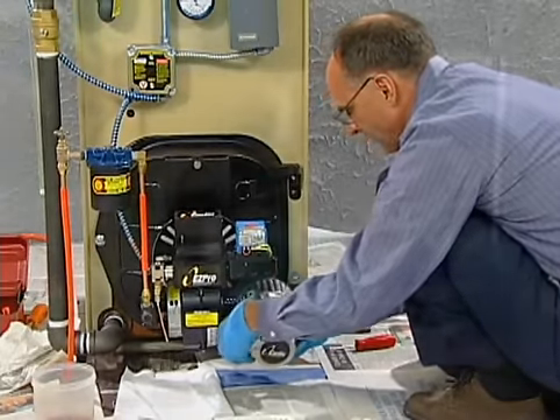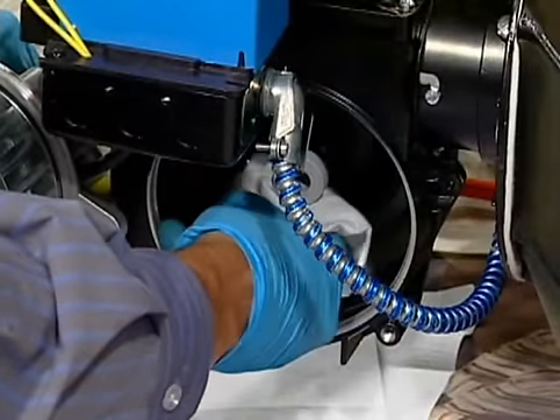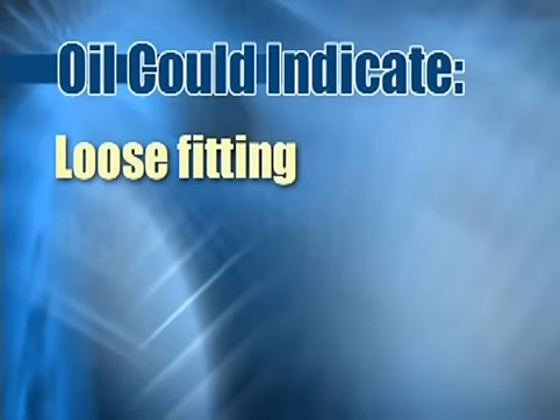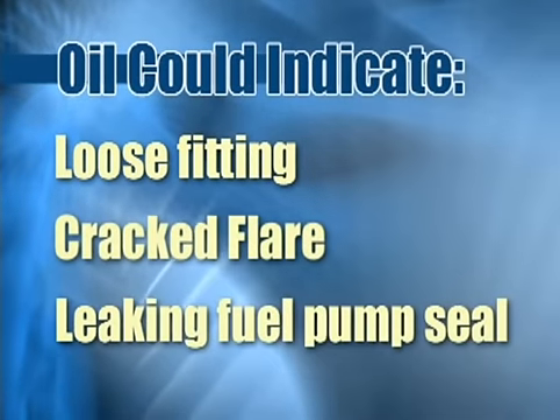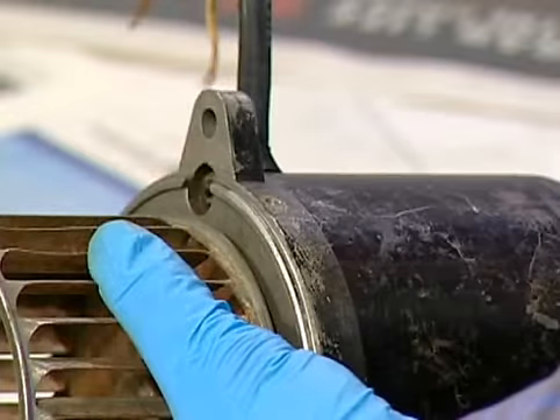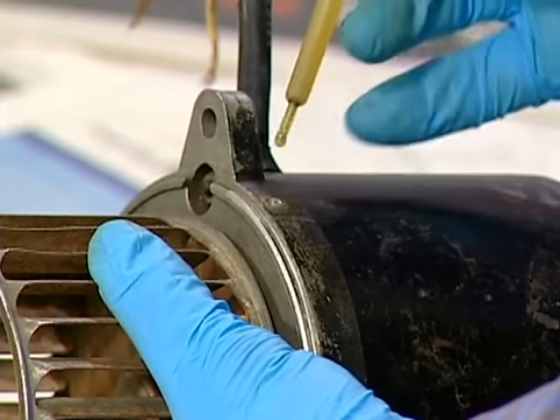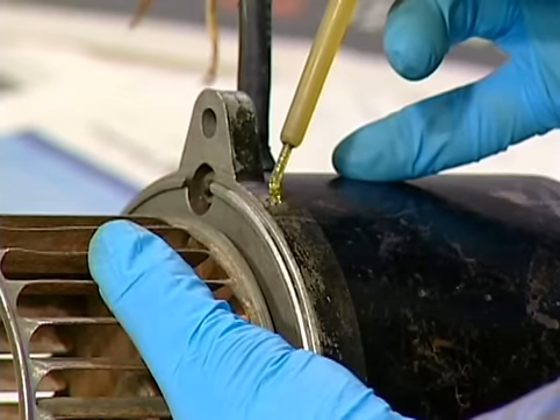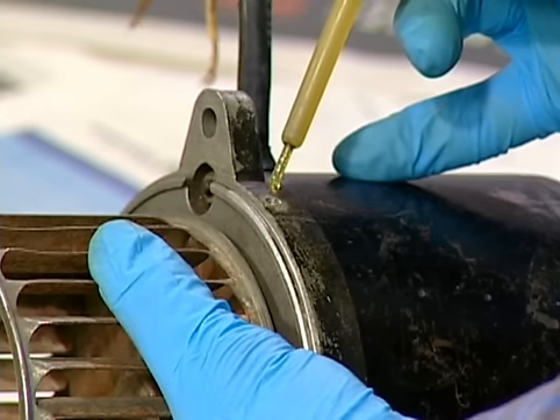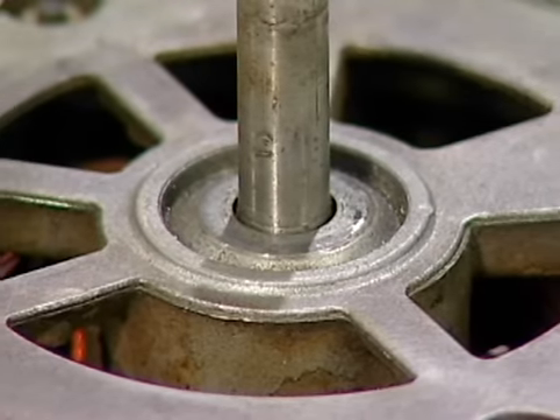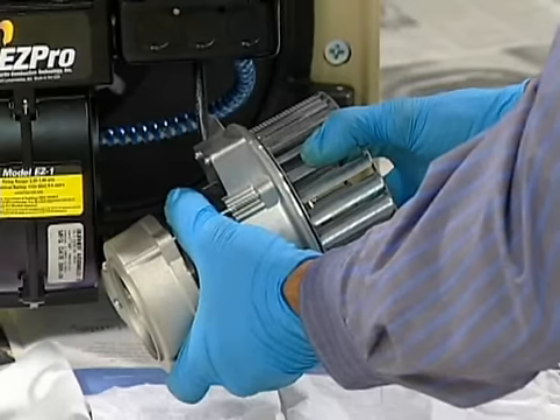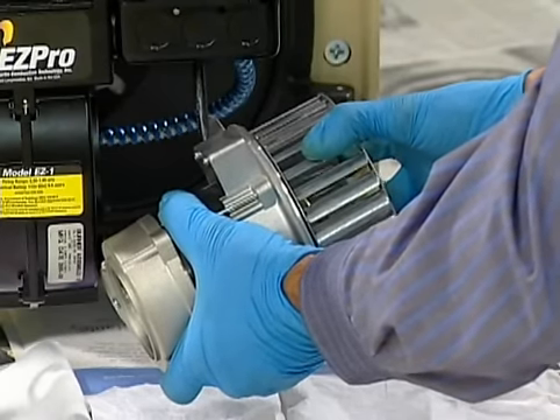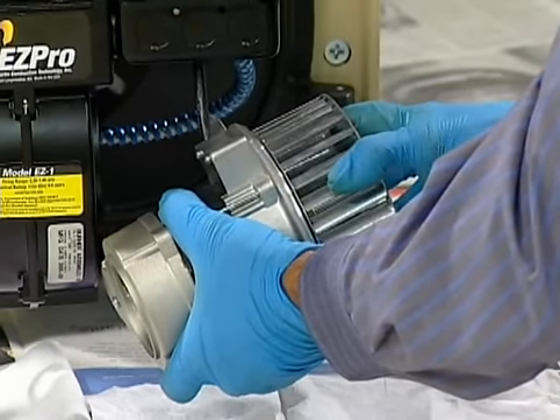Remove the burner motor and check the burner housing for oil, which could indicate a loose fitting, cracked flare, or leaking fuel pump seal. If there are oiling points on the motor, lubricate each with 3 to 4 drops of SAE 20 non-detergent oil. Cooling slots should be clear. Check the motor shaft for end play. If it's excessive, replace the motor.